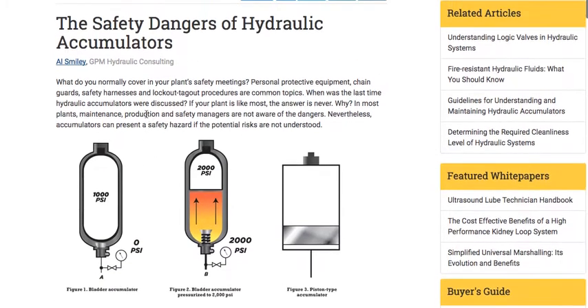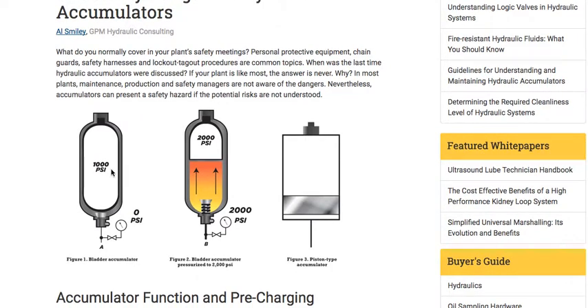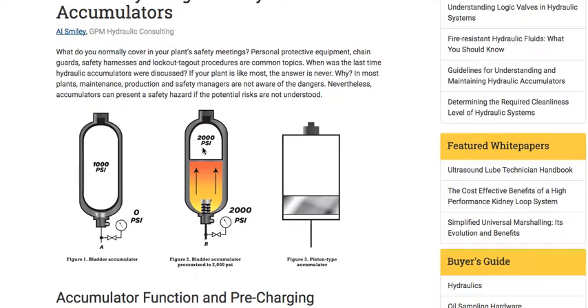There's also the bladder type, which works very similarly, except instead of a piston, it uses a balloon. As you can see here where it says 1,000 psi, this is if the accumulator had no hydraulic fluid in it — it's forcing all the hydraulic fluid back into the system when pressure is very low. In the event shown at 2,000 psi, the hydraulic fluid is being forced into the accumulator to take on extra pressure the system does not need. The pressure goes up because as the air is compressed, it's confined into a smaller and smaller space.